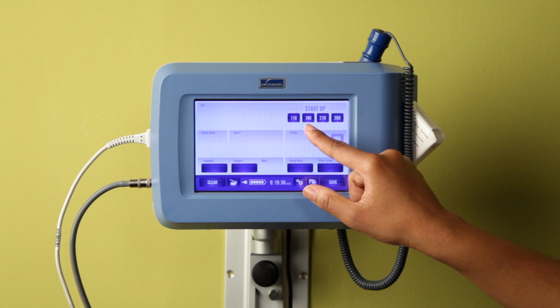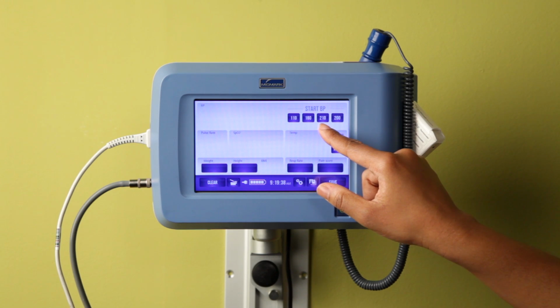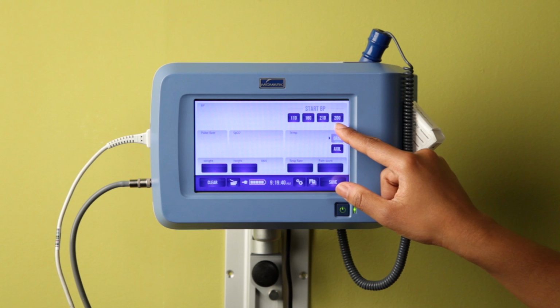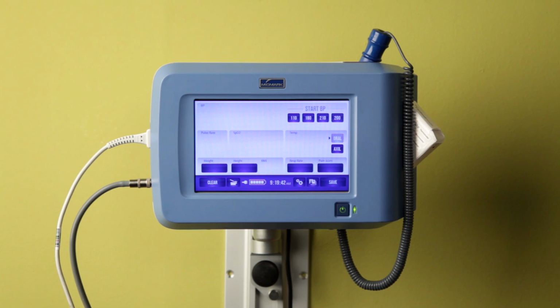Ideally, the initial inflation cuff pressure should be about 30 millimeters of mercury above the patient's systolic pressure. Using a higher pressure may cause the patient unnecessary discomfort, while choosing a pressure that's too low may cause the device to reinflate the cuff in order to obtain a systolic pressure.